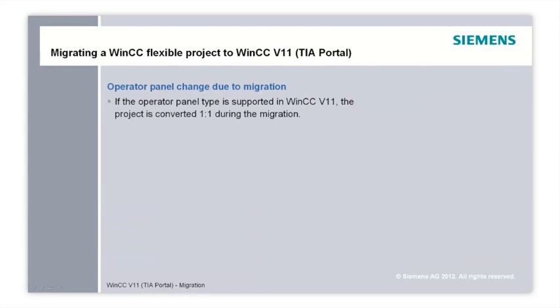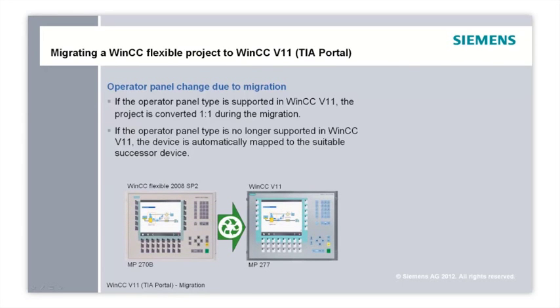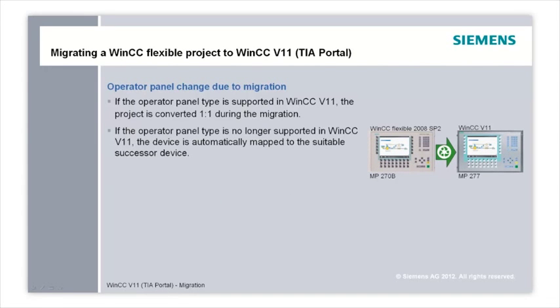What happens to an operator panel during migration? If the operator panel type in the WinCC flexible project is also supported in WinCC version 11, the project is converted one-to-one during the migration. If the type of the operator panel to be migrated is no longer supported in WinCC version 11, the device is automatically mapped to the suitable successor device. In the displayed example, the MP270B is migrated to the MP277 Key. WinCC version 11 also supports you regarding settings such as screen resolution or arrangement and size of the elements on the display.